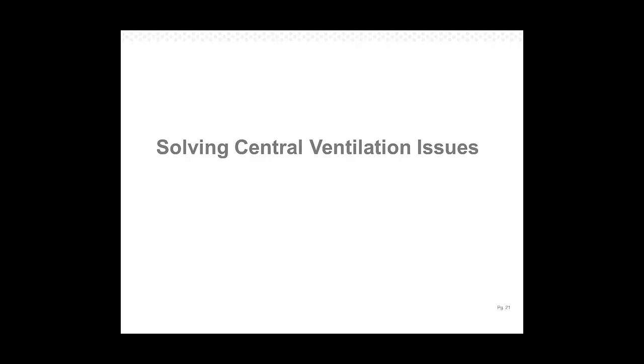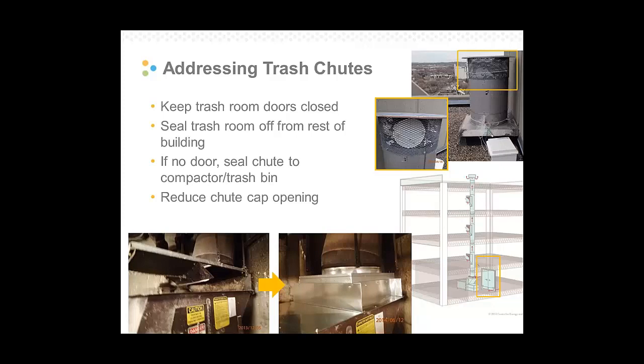So I'm going to go into a little bit about how we're solving these ventilation issues. What it boils down to is reducing excessive ventilation flow to get the energy savings, but then also balancing the flow so that it's adequately distributed throughout the building, so it's effectively dealing with moisture and odors and pollutants. Starting with trash chutes.